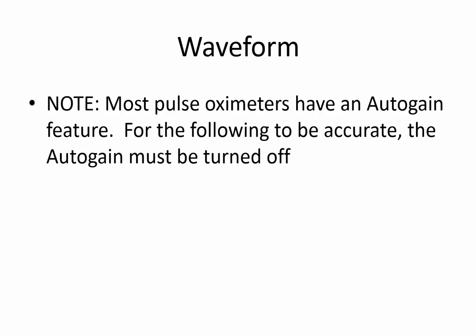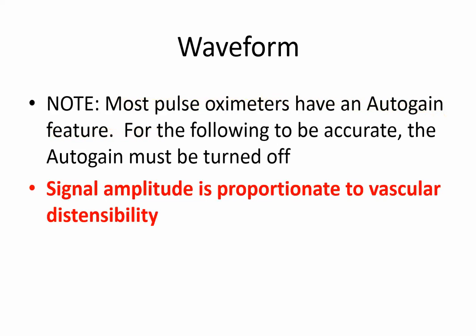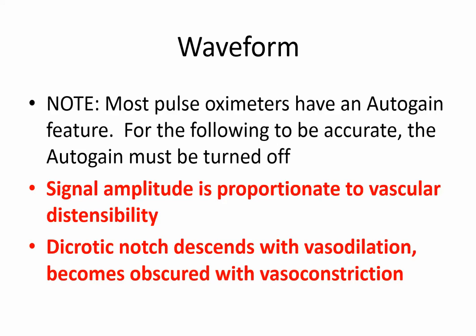When you think about waveforms in a pulse oximeter, you have to understand that most of the current pulse oximeters have an auto gain feature in them. For the comments that follow, this auto gain feature must be turned off. The signal amplitude is proportionate to vascular distensibility. I'll say that again. The signal amplitude is proportionate to vascular distensibility. I see that as a question on the test. The dicrotic notch descends with vasodilation and becomes obscured with vasoconstriction.